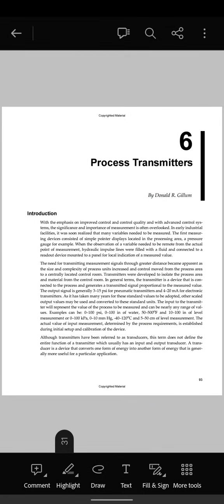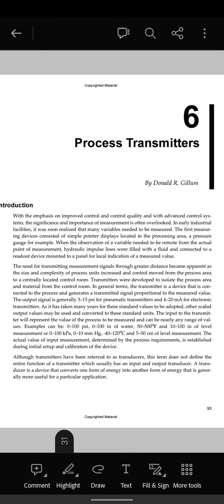Process transmitters. Introduction. With the emphasis on improved control and control quality, and with advanced control systems, the significance and importance of measurement is often overlooked. In early industrial facilities, it was soon realized that many variables need to be measured. The first measuring devices consisted of a simple pointer display located in the processing area, a pressure gauge, for example, when the observation of a variable needed to be remote from the actual point of measurement. Hydraulic impulse lines were filled with a fluid and connected to a readout device mounted on a panel for local indication of a measured value.